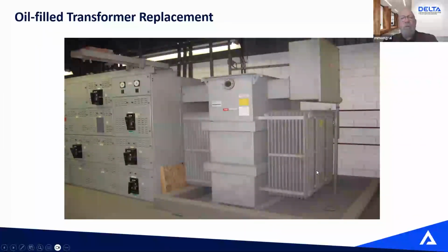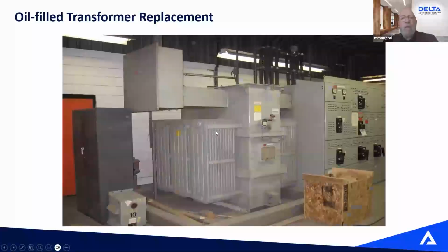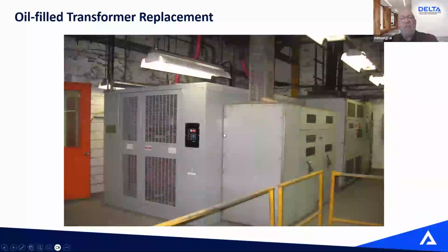Those are a few pictures of a project we did. There were 6 or 7 liquid fill units in a paper mill up north Quebec. So those liquid fill transformers were removed and some dry type were put in place. So of course, there's a lot of work involved. You have to break down this tank or this basin if you have leakage, and you have to build a housekeeping pad. But at the end, that's the result.